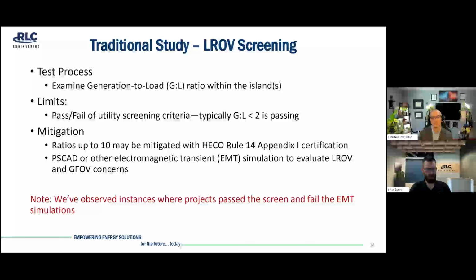One thing to note is we have seen instances where projects passed either due to the generation to load ratio or they were mitigated by HECO. However, they failed once they got to the EMT simulations. Now, it's hard to say whether that was because the EMT model wasn't necessarily representative of the actual device, or whether they did in fact fail these LROV concerns. But something we've taken to do is, if we're already running the EMT simulations, even if the screen passes, we will sometimes double check these LROVs.